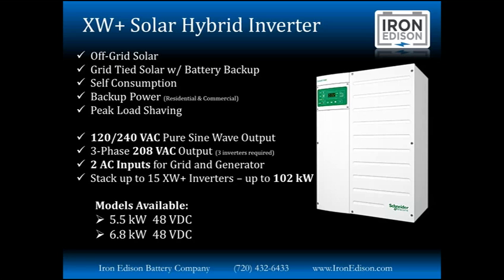There are 2 main models available, a 5500 watt or 5.5 kilowatt 48 volt inverter, as well as a 6800 watt or 6.8 kilowatt inverter charger. Both of these inverters are capable of delivering twice this amount of energy for 15 to 30 seconds. This would allow you to start heavy loads like a motor or a pump or an air conditioner. It's also valuable in peak load shaving applications.